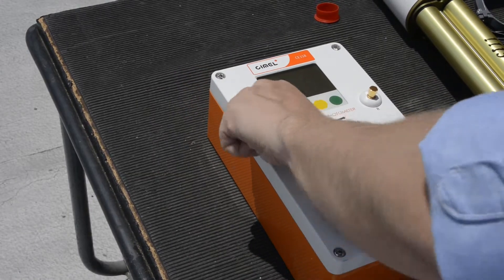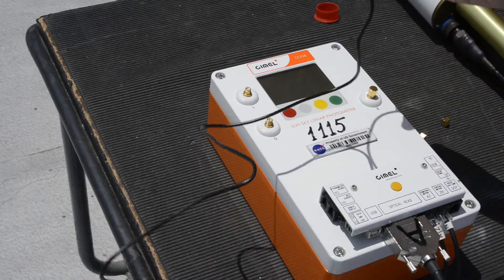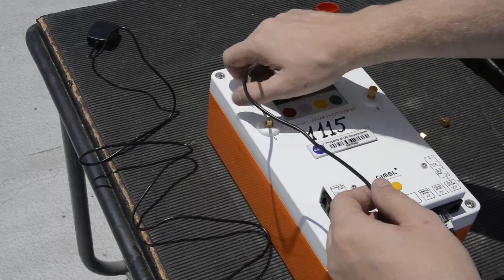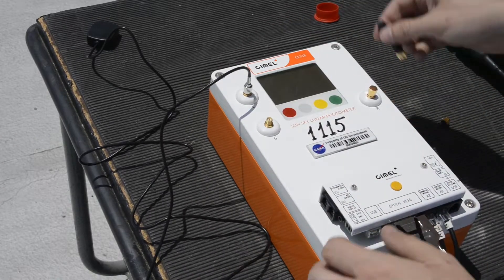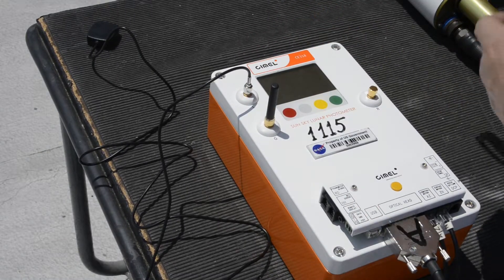The two SMA connectors on the left side of the control box are labeled G and L. L is for location, G is for GSM. Connect the location antenna to the connector labeled L. If your instrument is set up for GSM, connect the GSM antenna to G.